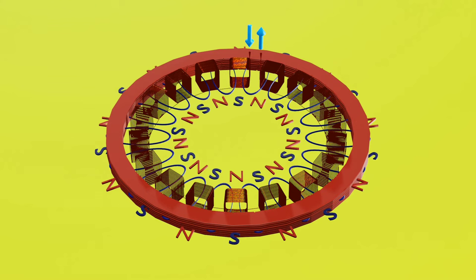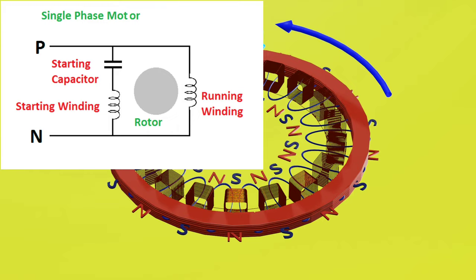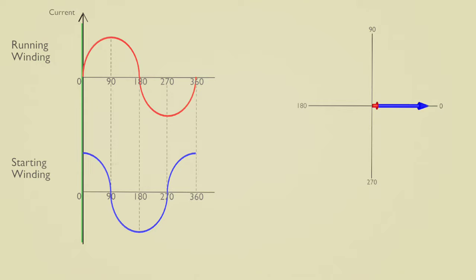So to overcome this problem, to give starting torque to our fan, we use second winding or starting winding and a capacitor. The capacitor is put in series with starting winding. This whole arrangement is in parallel with running winding. How does this arrangement work? Let's see.